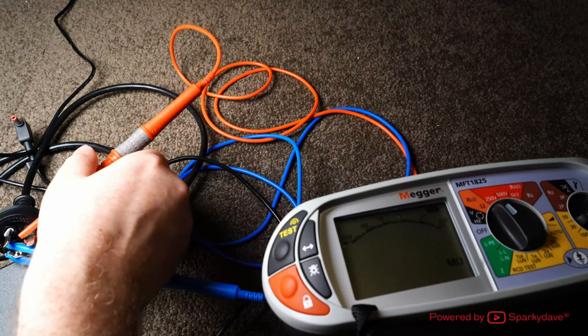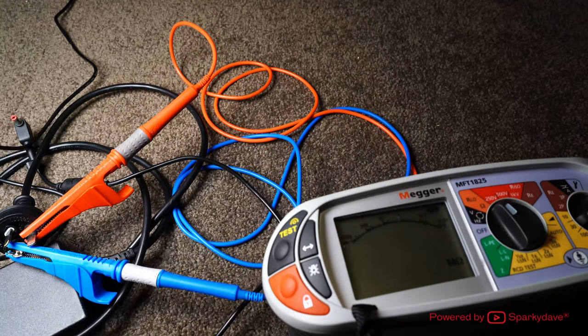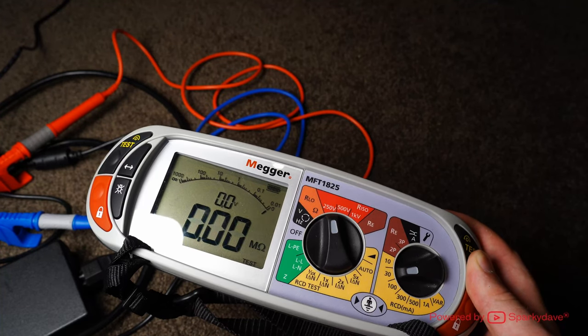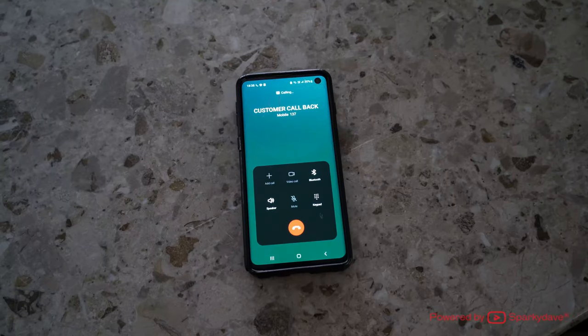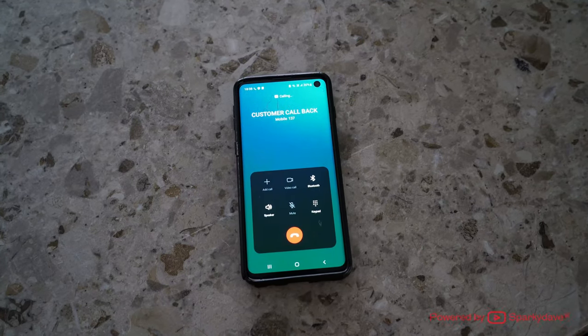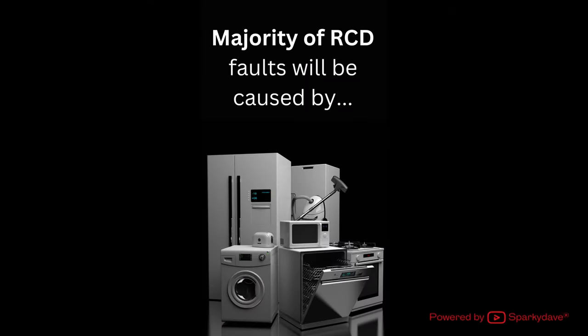It's a good idea to test the appliance on site and verify the correct diagnosis has been made, as most electricians do not want a callback. The most common appliances that fail and cause the RCD to operate are, by far and most commonly, a laptop charging cable.